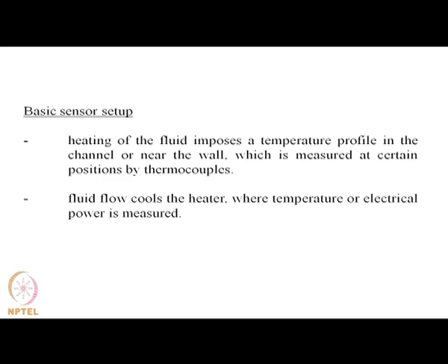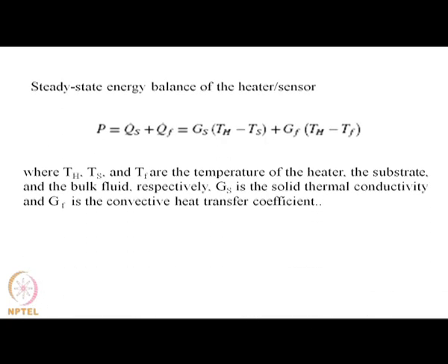So, the basic sensor setups can be of two types. One is that the heating of the fluid is going to impose a temperature profile in the channel or near the wall, which is measured at certain positions by thermocouples or some such sensors. The fluid flow cools the heater, where temperature and electrical properties are measured. So, let us look at the energy balance for such cases.